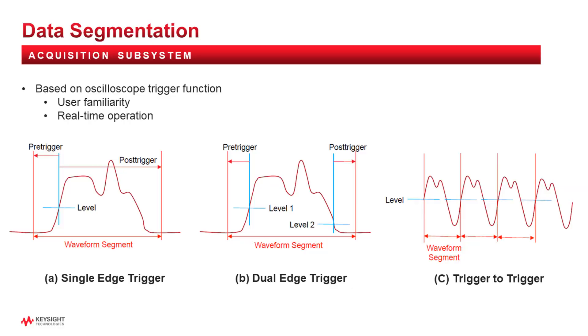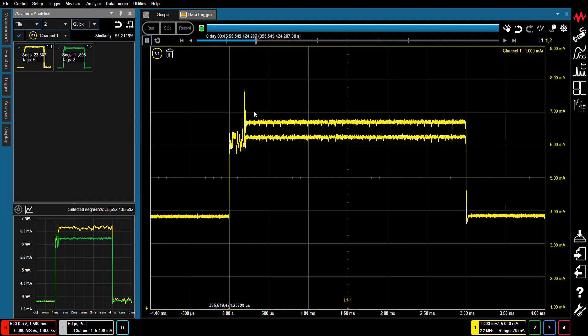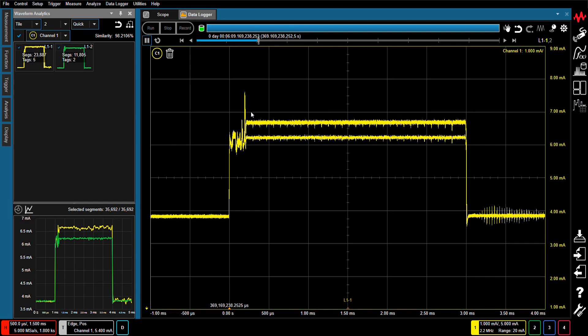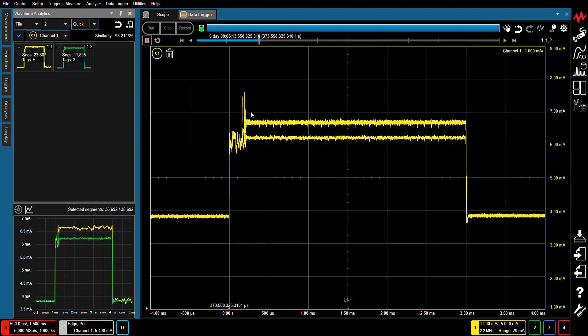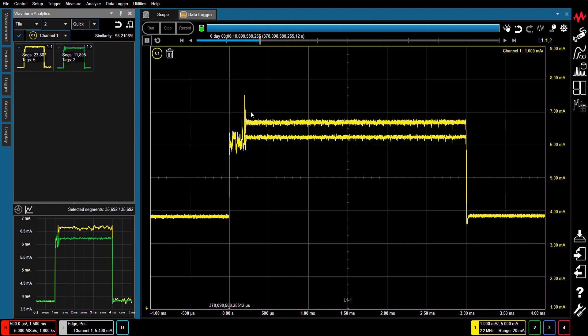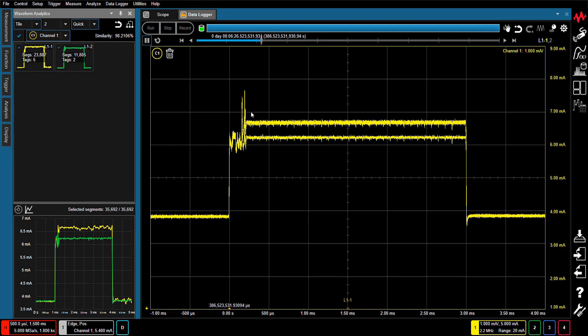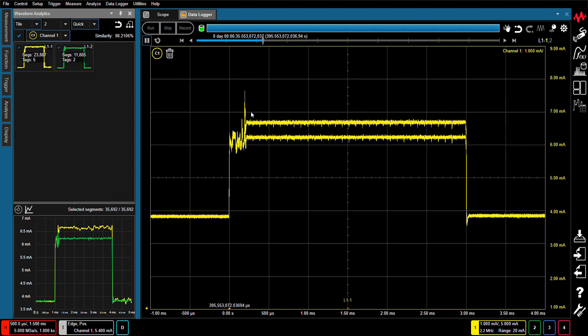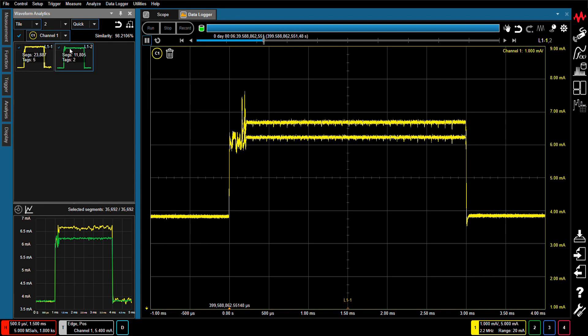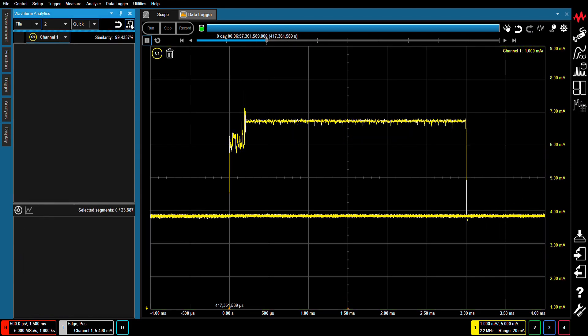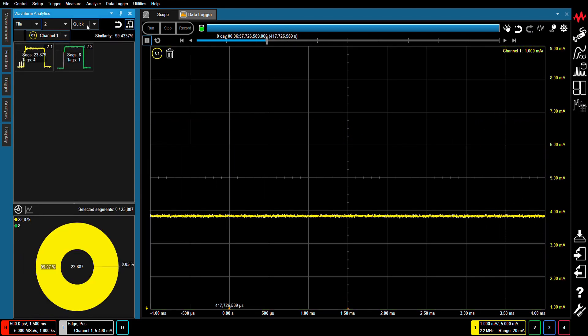Waveform segments are defined using various combinations of the triggering functions. The Anomalous Waveform Analytics feature can extract and classify waveforms concurrently as it is recording live long duration measurement data. This allows you to view classified waveform information immediately after the measurement is complete without the need to wait for any post-processing analysis.